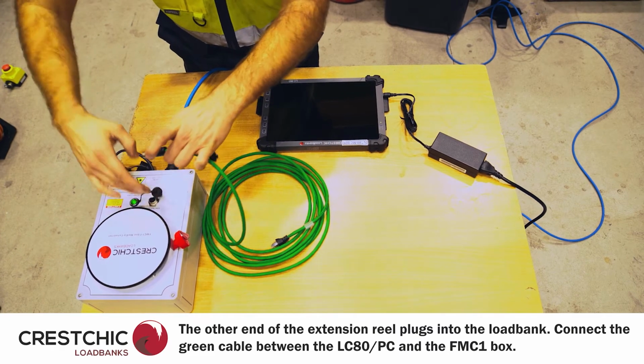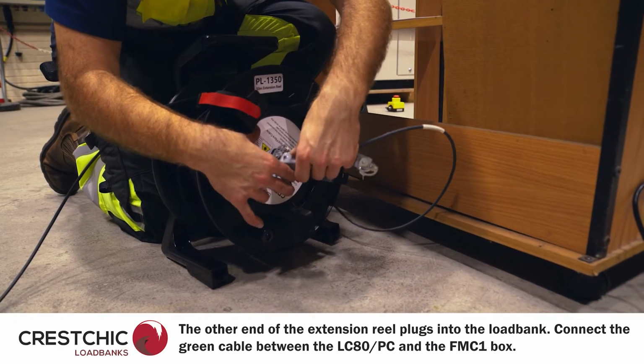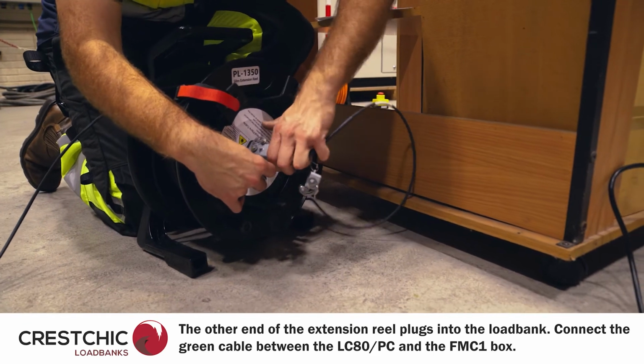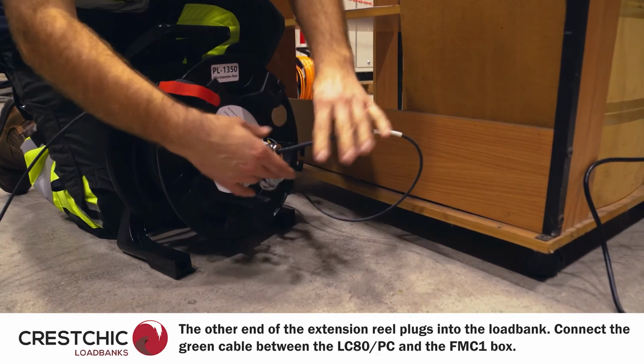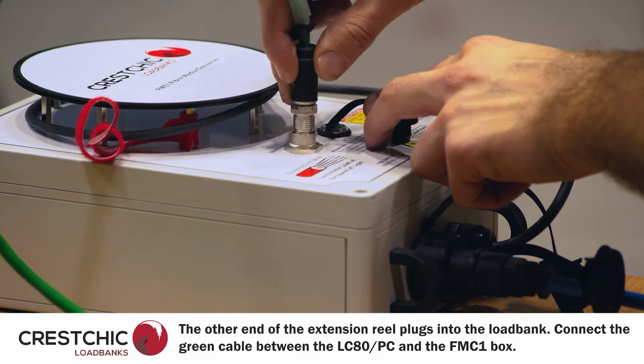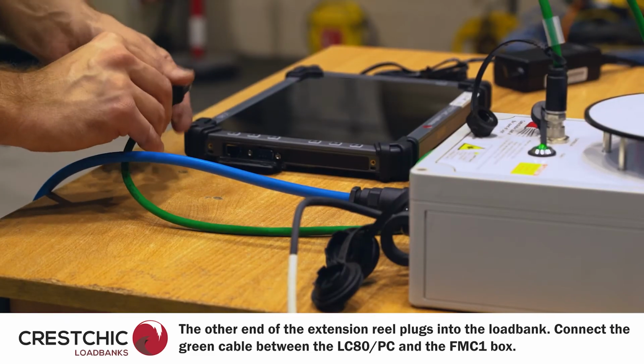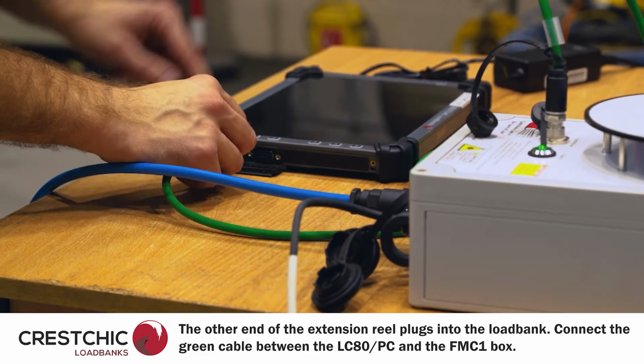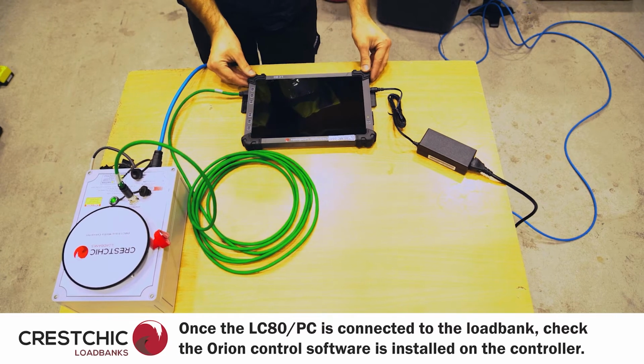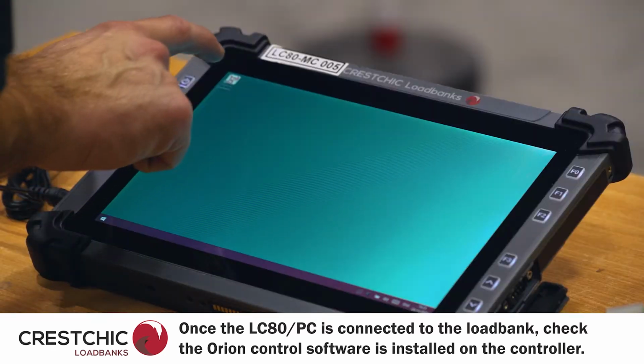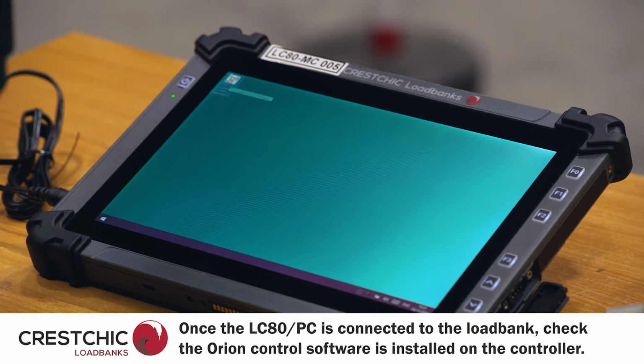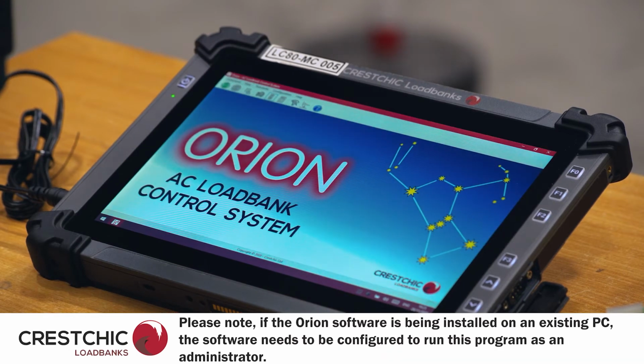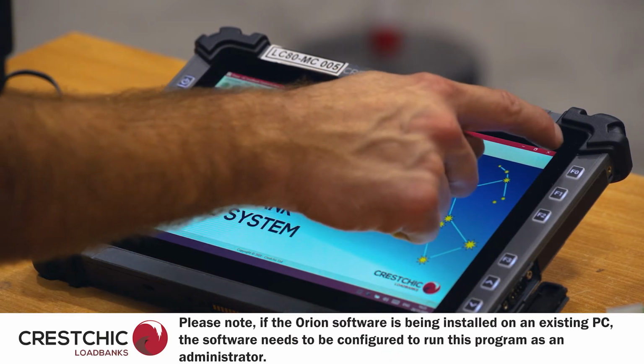If this is the case, a fibre extension cable reel will be used. This connects between the load bank and the FMC1 box. A cable is then connected between the LC80 or PC and the FMC1 box. On the LC80 or PC, the software required to control the load bank and complete the commissioning of the load bank is called Orion. At this stage, it is a good idea to check this is present on the controller.